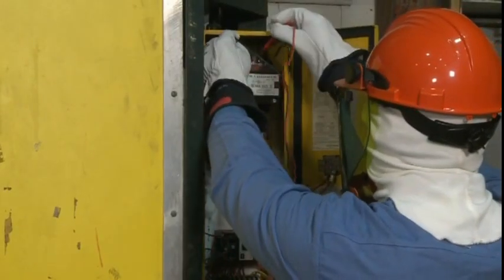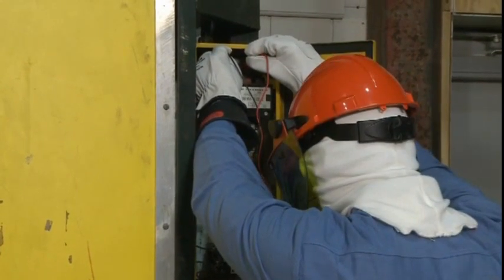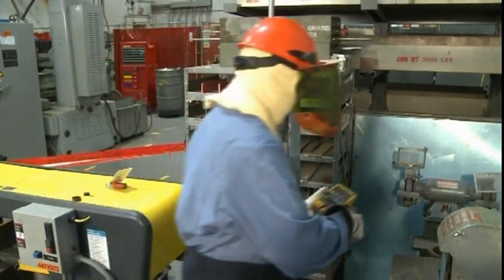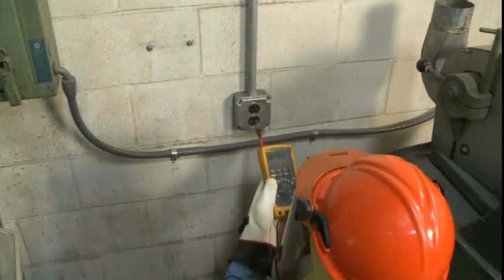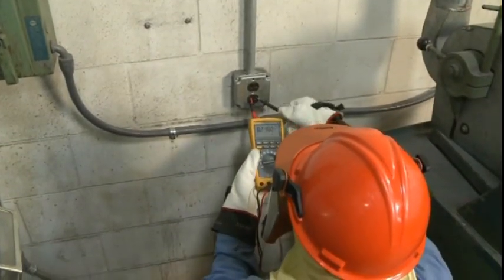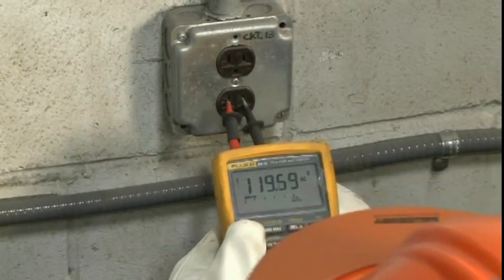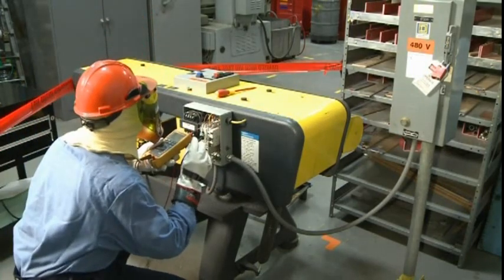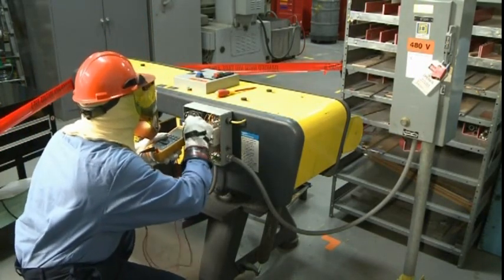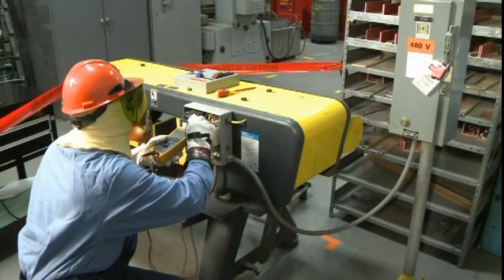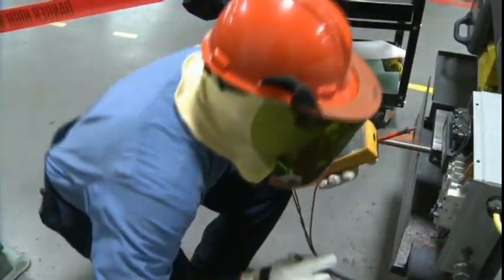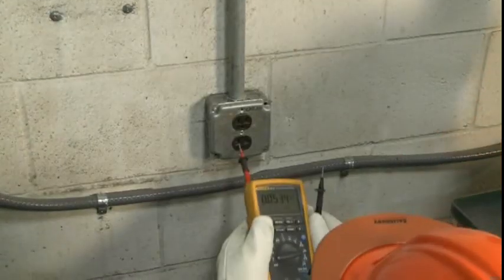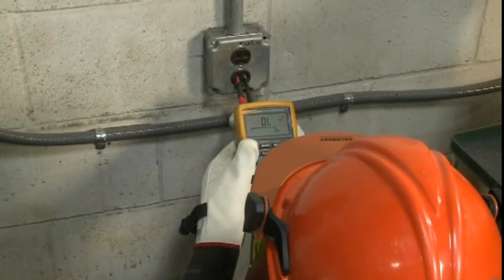Testing for a zero energy state must be done using a known working voltmeter. This is why you must verify your voltmeter is functioning properly by measuring a known voltage source immediately prior to voltage testing. To confirm a zero energy state, test each phase conductor or circuit part, both phase to ground and phase to phase, for all phases. Then, test your meter again on a known voltage source. Testing your meter before and after voltage testing ensures that a broken meter won't incorrectly verify a zero energy state.